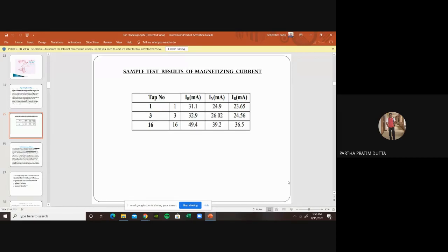If in proper testing the magnetizing current comes to 6 to 10 milliampere, that is okay for us. But in the case of old transformers, it may go to 30 milliampere and beyond, but it should not go to the ampere range. If it is in the ampere range, then we say that the magnetizing current is faulty and the core is not acting properly.